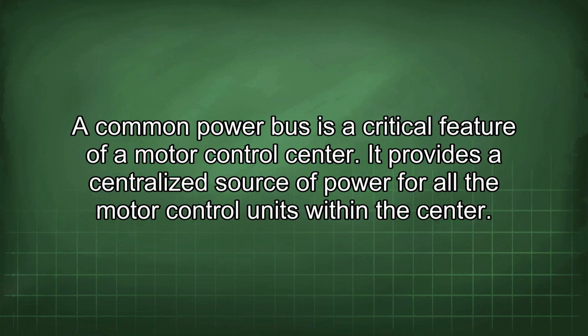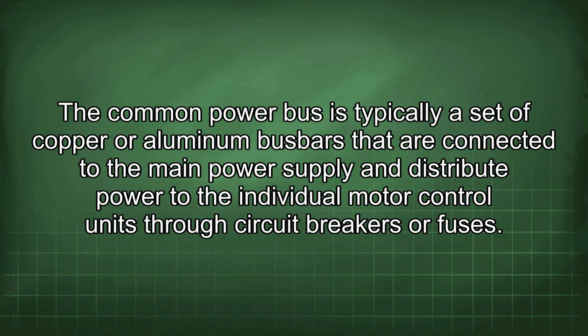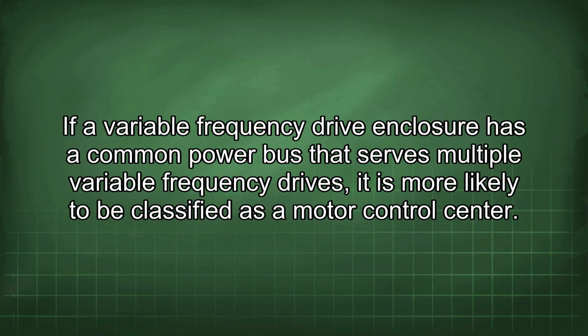A common power bus is a critical feature of a motor control center. It provides a centralized source of power for all the motor control units within the center. The common power bus is typically a set of copper or aluminum busbars that are connected to the main power supply and distribute power to the individual motor control units through circuit breakers or fuses. If a variable frequency drive enclosure has a common power bus that serves multiple variable frequency drives, it is more likely to be classified as a motor control center.